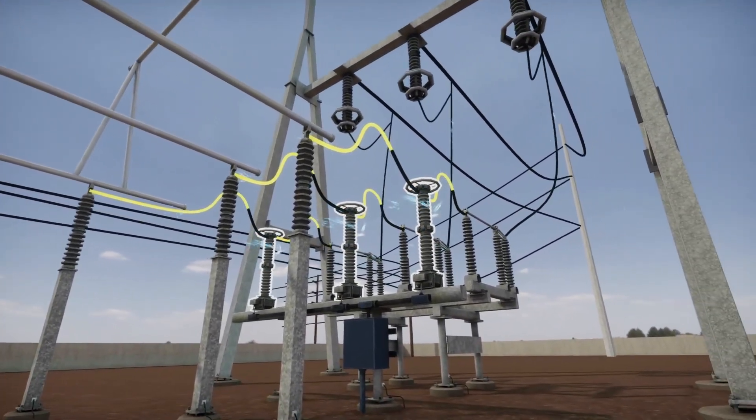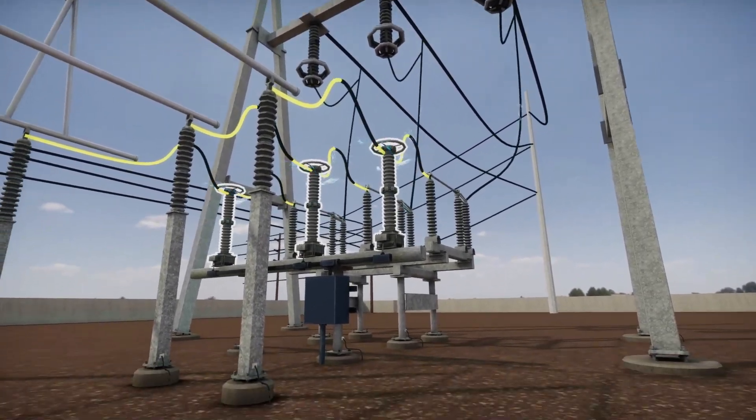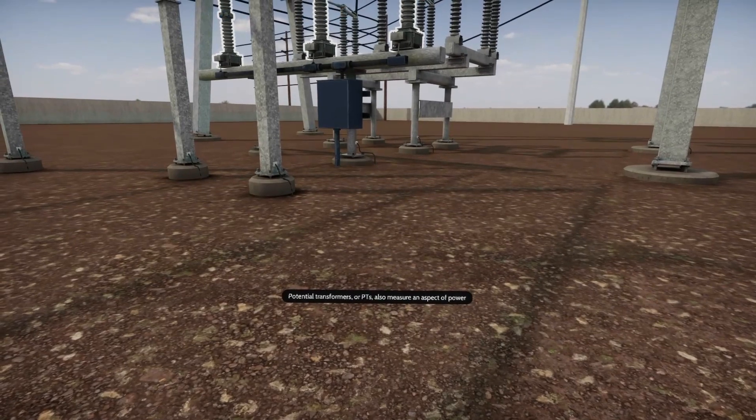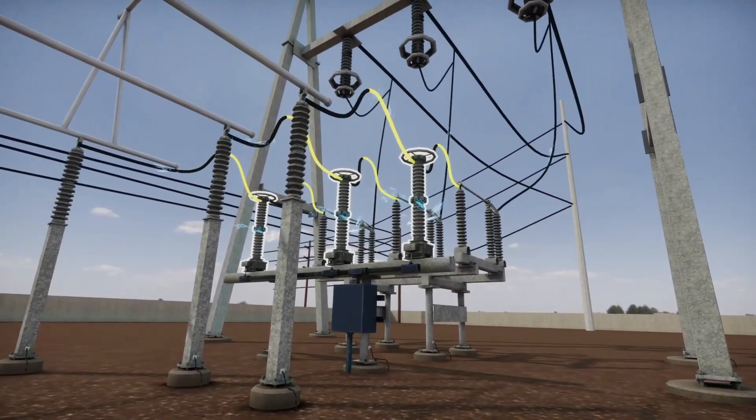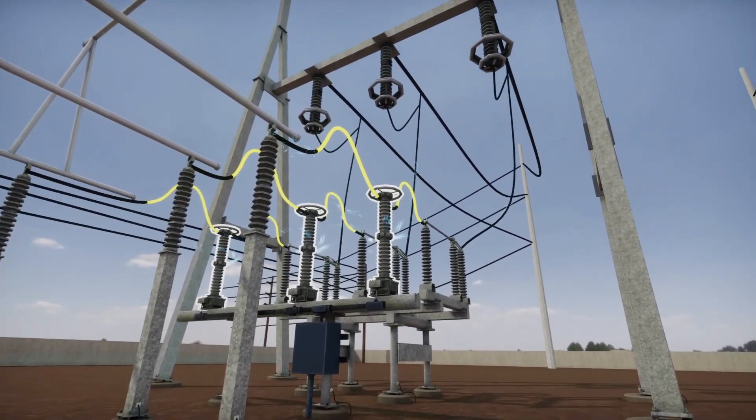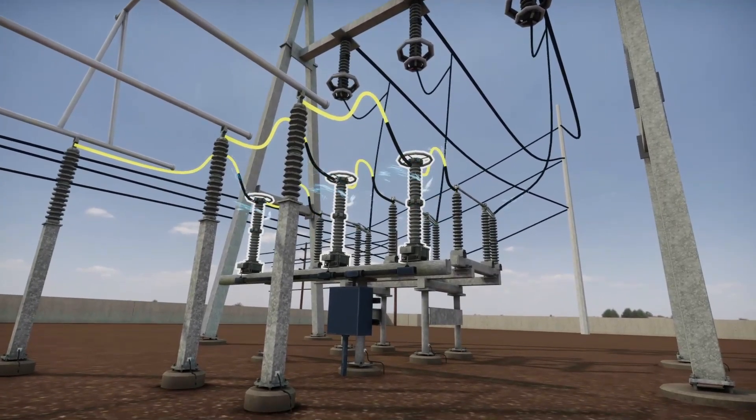Current transformers, also known as CTs, are used to measure alternating current. Potential transformers, or PTs, also measure an aspect of power supply. But while CTs measure current, PTs measure voltage. Both reduce the high voltage and current to an amount that can be recorded by instrumentation.